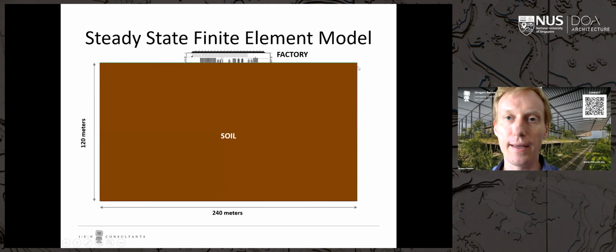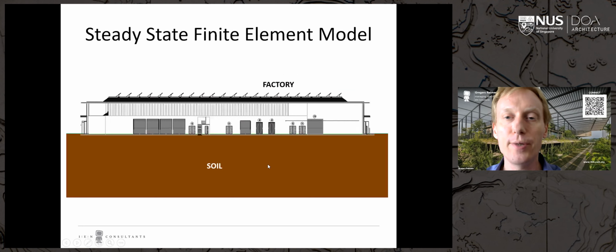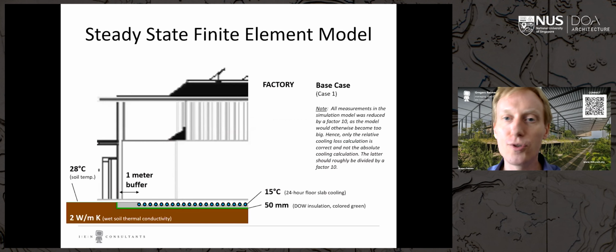We did some interesting studies on the insulation required for this factory, since we're basically cooling the whole floor. We built a model with all the soil below the factory and looked at how much insulation should be put in the floor. As an initial estimate, we put 50 millimeters of insulation across the whole floor, with the chilled water pipes placed accordingly.